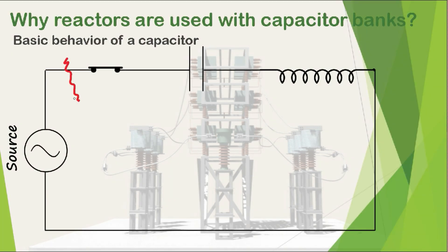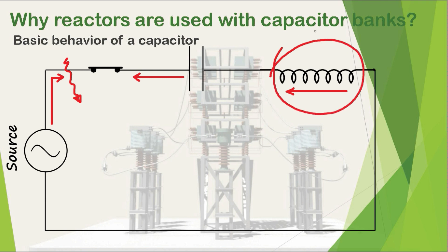Suppose a fault occurs, so current will try to come from the system as well as from the fully charged capacitor. Since the capacitor is in a charged condition during the fault, it will try to discharge very rapidly due to the low-impedance fault path. But due to the presence of this reactor in the circuit, the discharging current during the fault will be limited, which will save the capacitor bank.